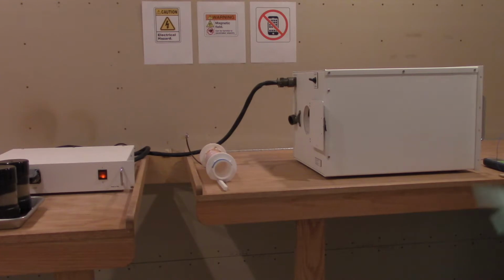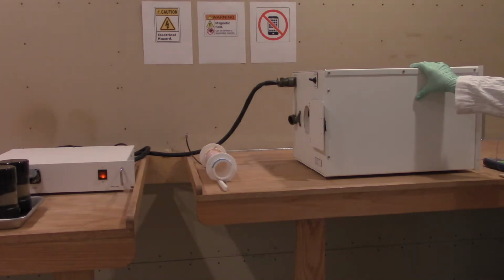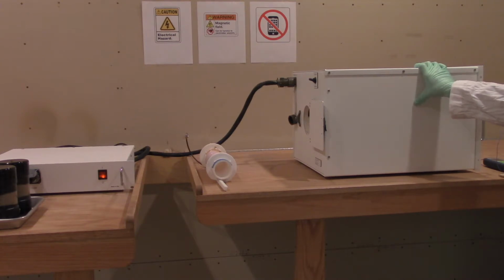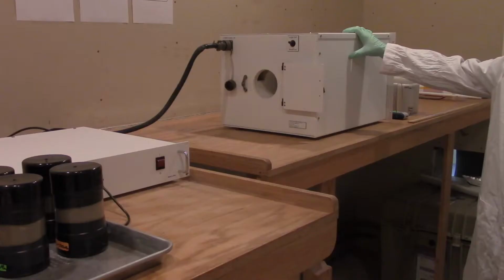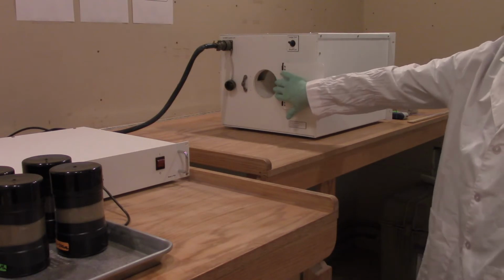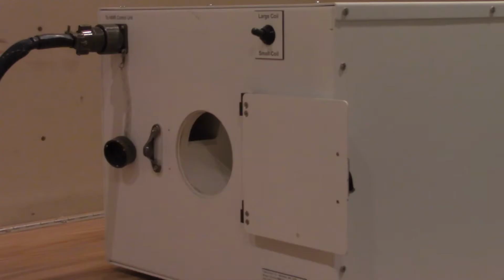We're going to start by discussing the parts of the instrument. This is the sensor. This is where the permanent magnets are and where the coils are that generate the excitation pulses. The sample goes into the sensor, in the port in the front of the sensor here.